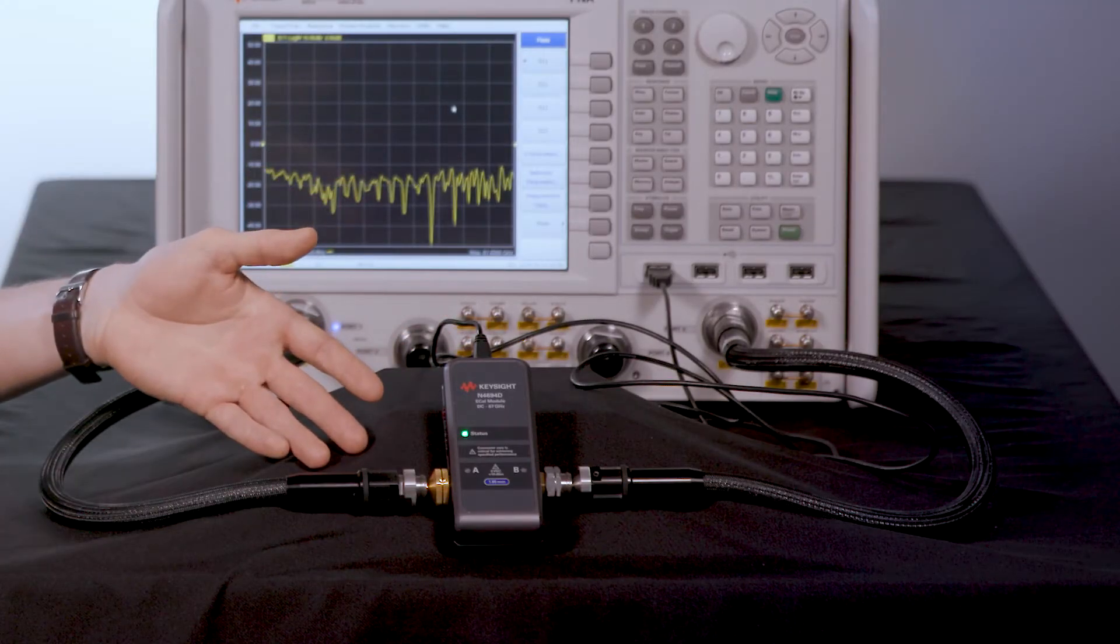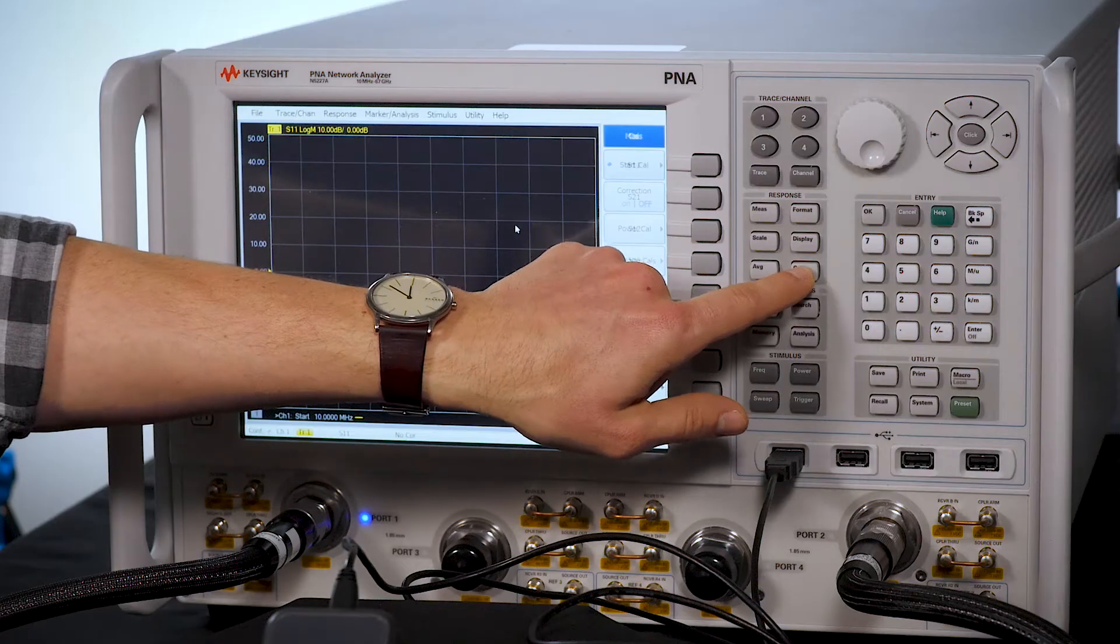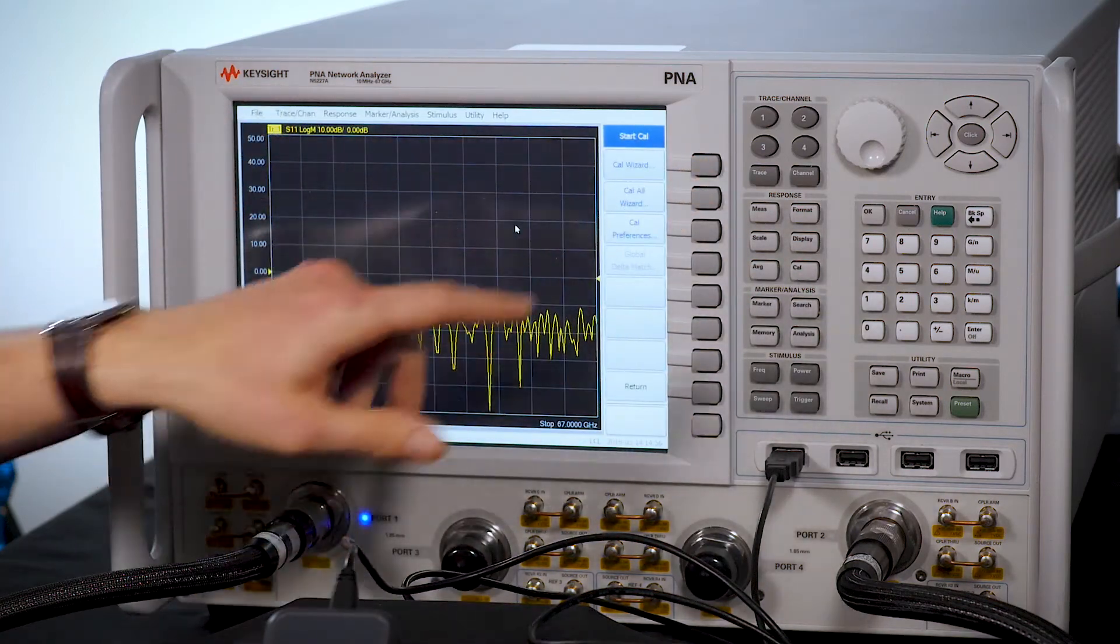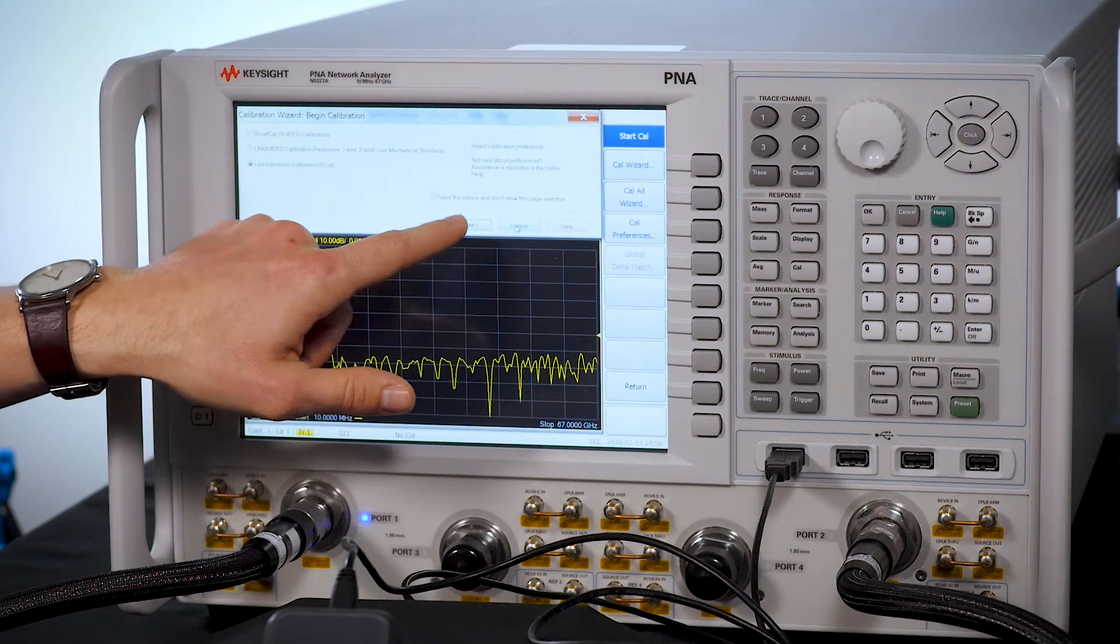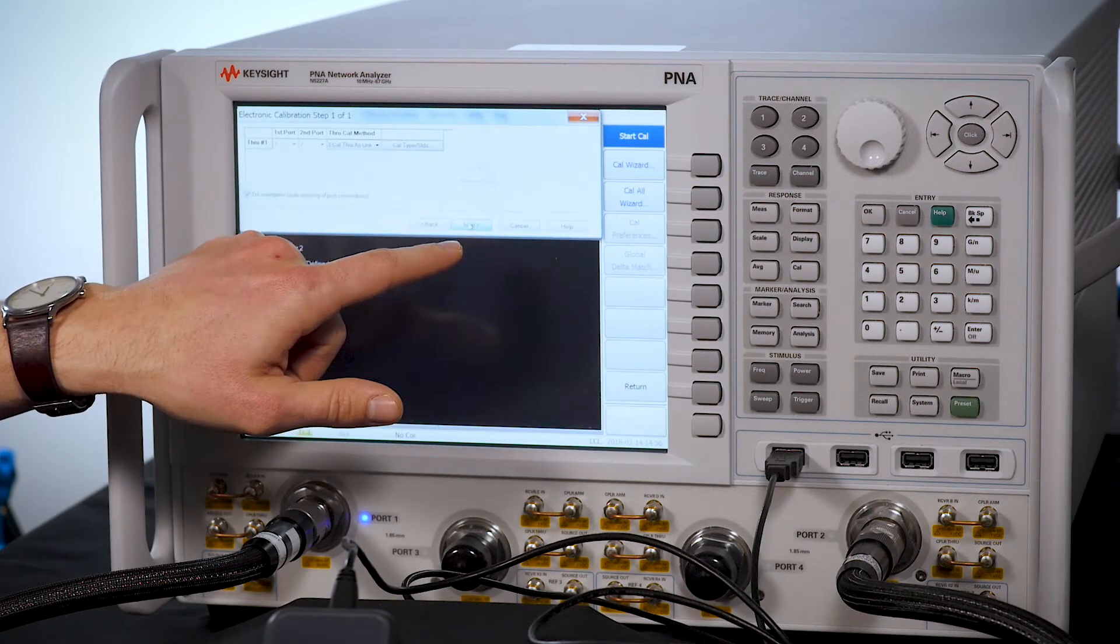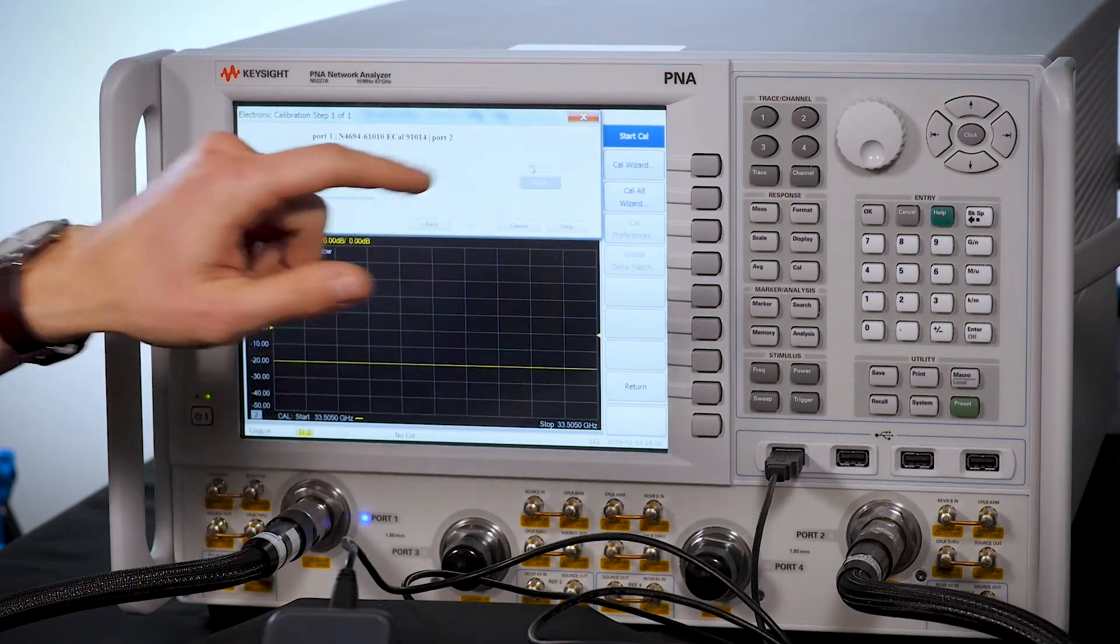To use an eCal, simply connect the USB cord and test cables. Go to the calibration wizard and select the type of calibration you would like to run. Follow through the steps of the wizard to customize your calibration. Once you finish setting up your calibration, go ahead and start it.